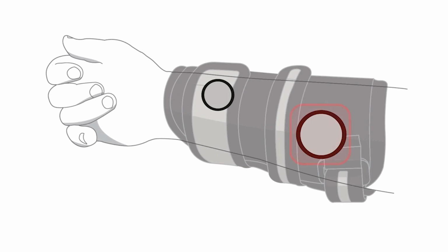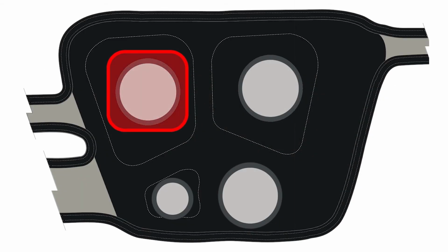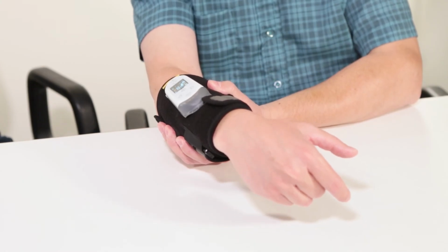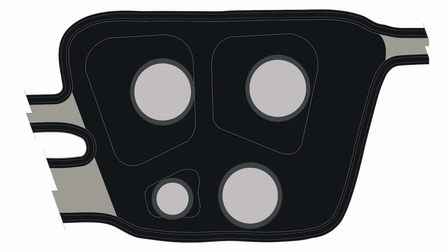The flexor electrode controls the grasping and is the electrode on the inside forearm muscle and in the large target area closest to the double strap. Just like the hand opening, you can adjust which fingers are being activated by adjusting the electrode inward or outward.